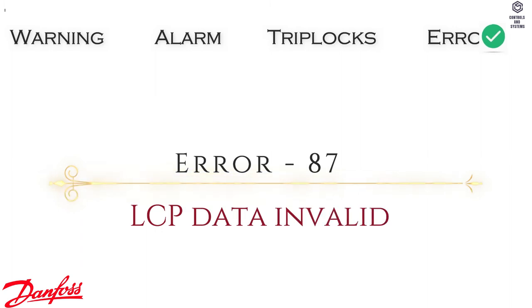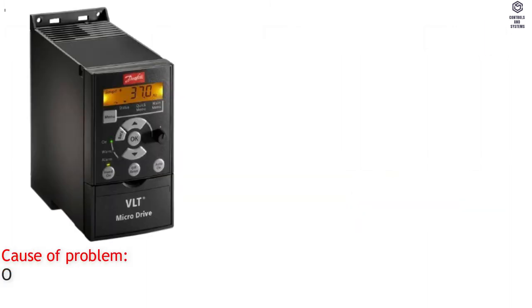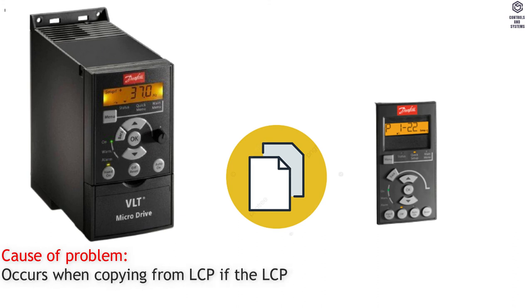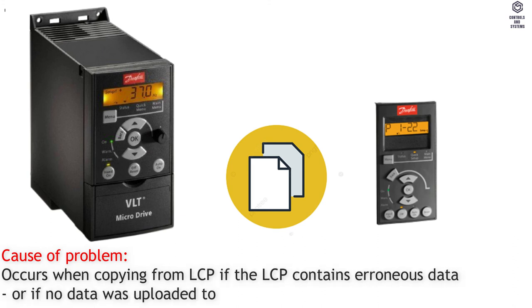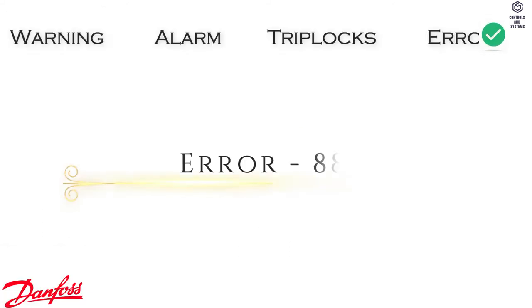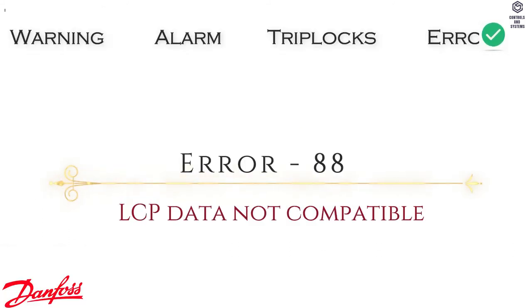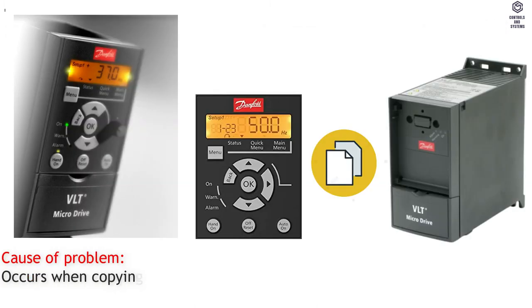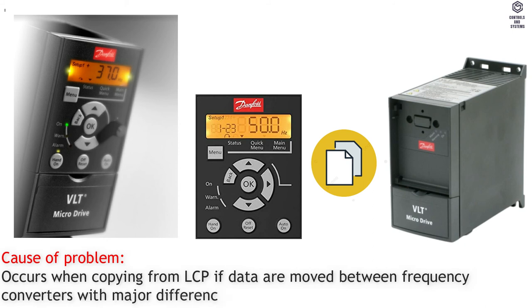Error 87: LCP Data Invalid. Cause of Problem — occurs when copying from LCP if the LCP contains erroneous data, or if no data was uploaded to the LCP. Error 88: LCP Data Not Compatible. Cause of Problem — occurs when copying from LCP if data are moved between frequency converters with major differences in software versions.